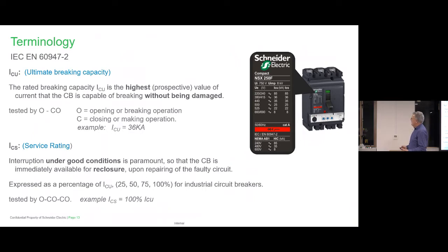This breaker has to be able to see a maximum prospective fault up to the value of its ICU value, in this case at 380, 415 volts, 36 kA. So that means it opens. Then you should be able to close it on that fault, and it opens again at this point. That value is what it's saying it can achieve.